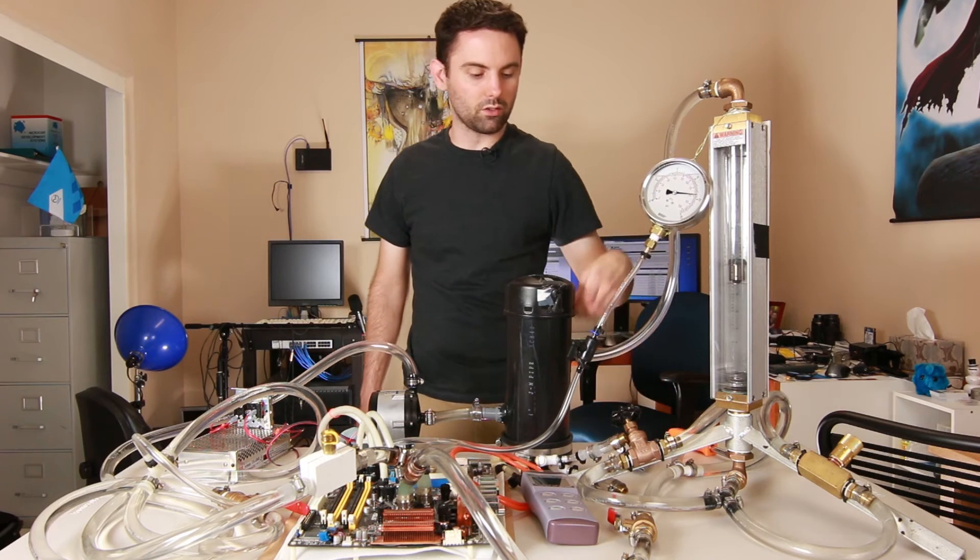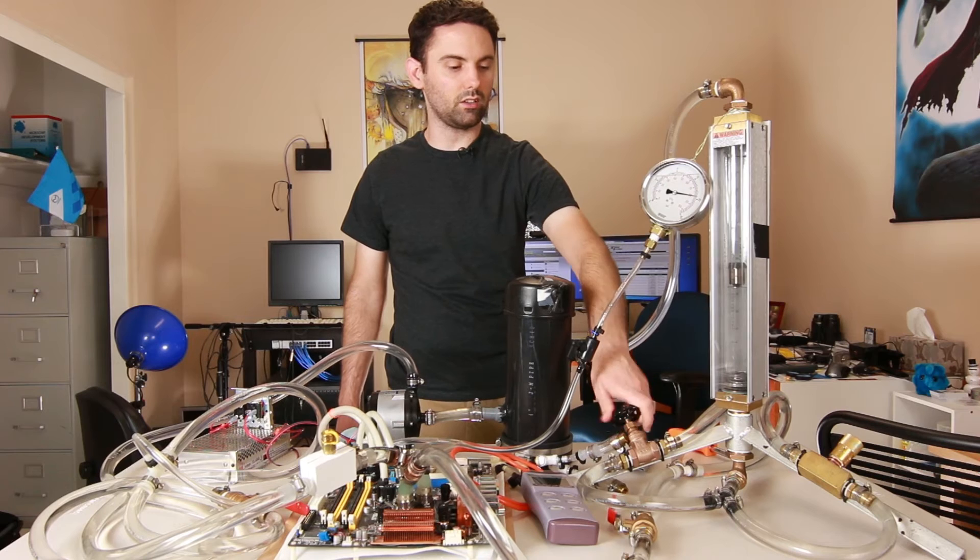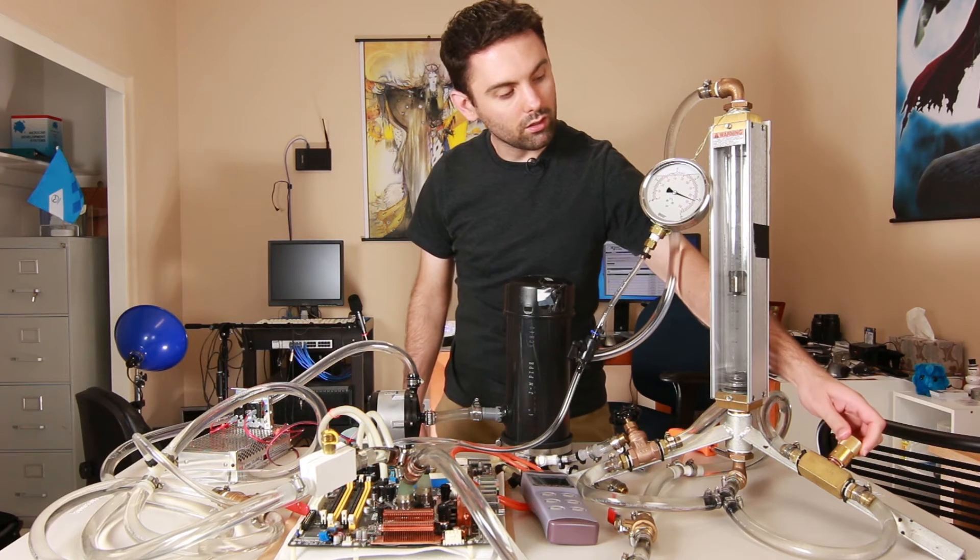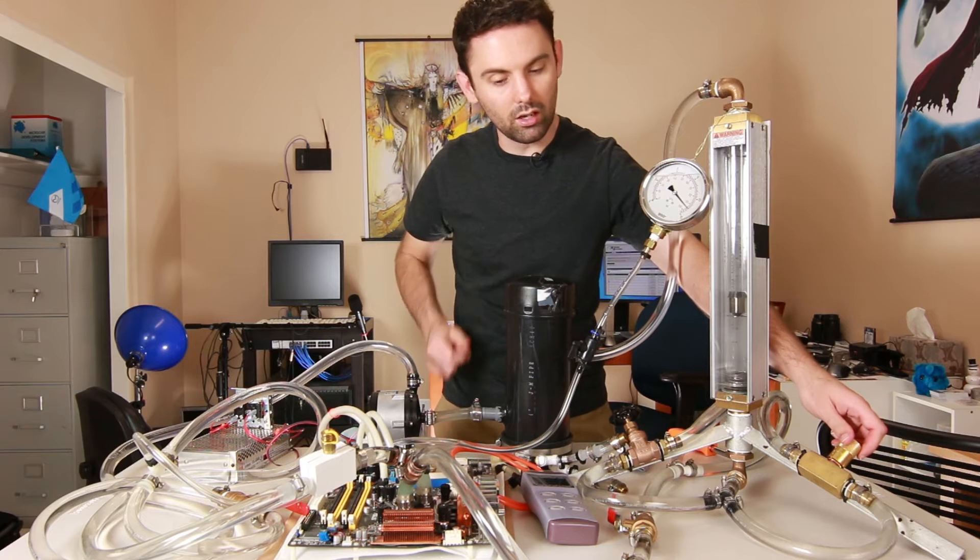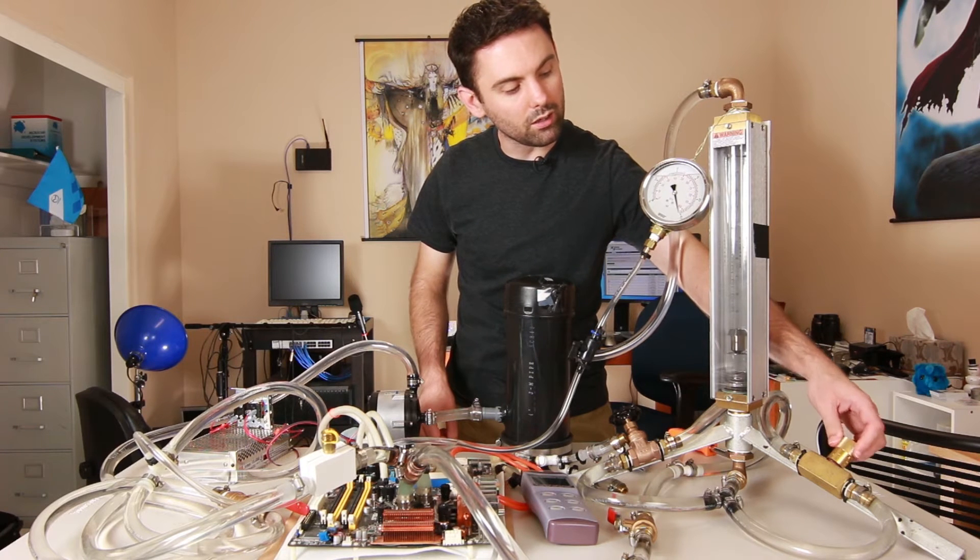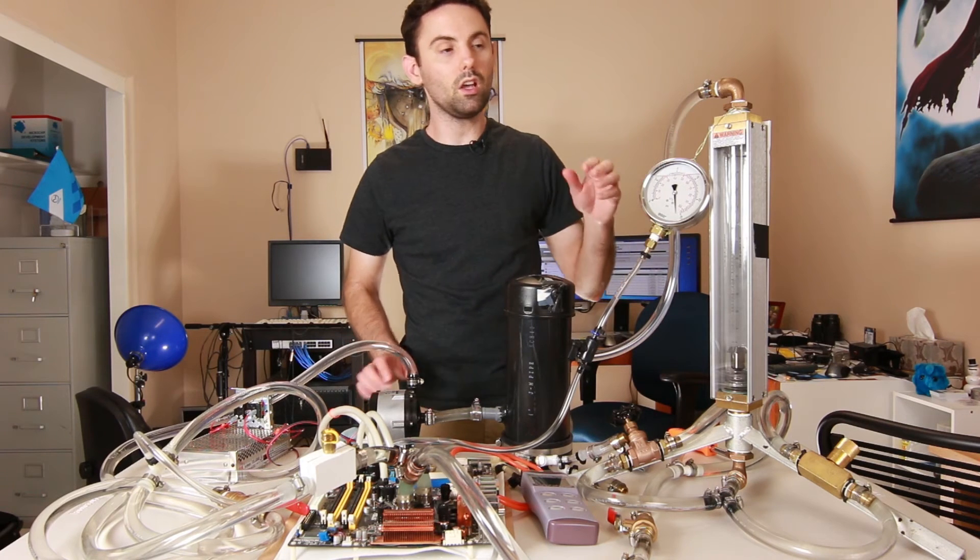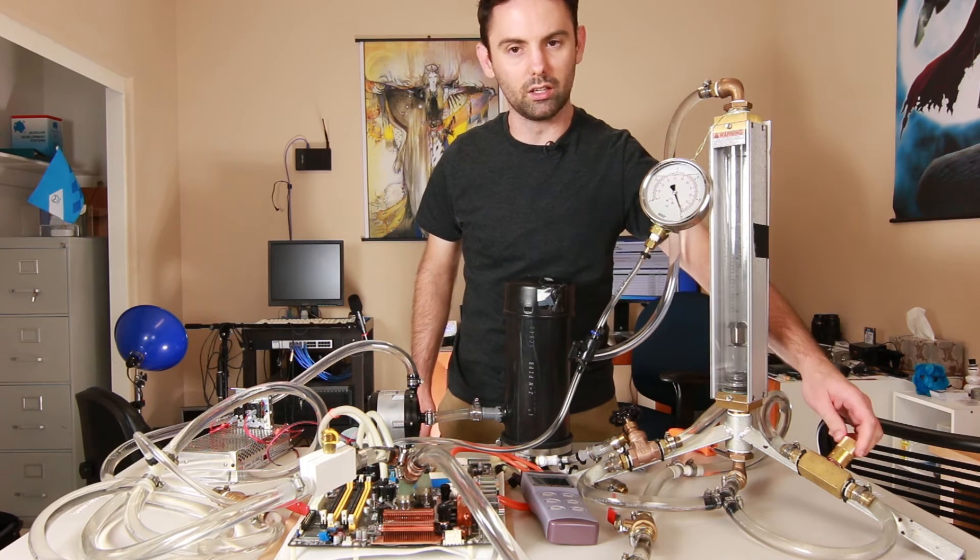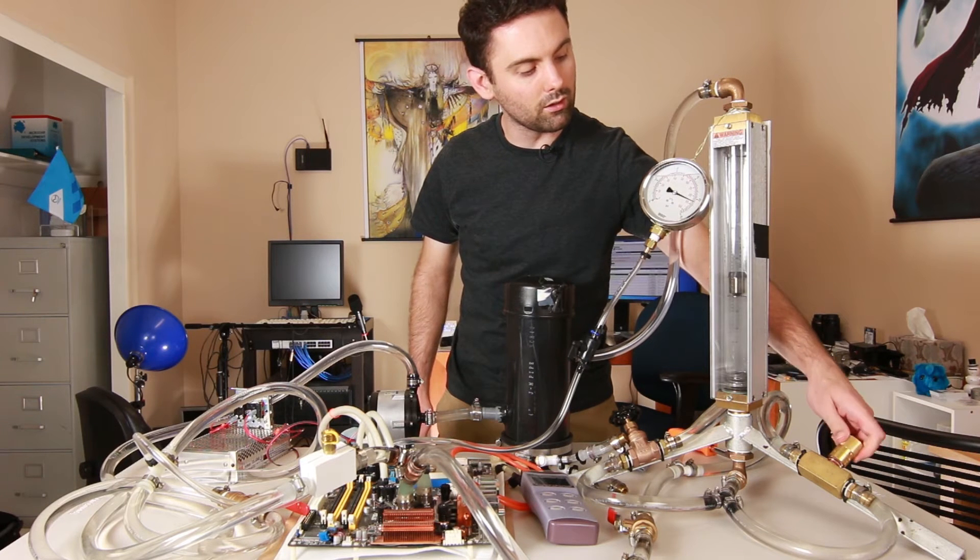Now if I start closing the valves, the control valves that I have on here, you'll note the float in the flow meter starts to descend, and it does so kind of slowly until I get to the needle valve over here. But as I close off the needle valve, it'll descend much more rapidly, and you'll see the pressure gauge increasing very quickly as I approach deadhead, which is basically when we reach zero flow, maximum head pressure. You'll see the gauge go off scale high, which it should be doing right, yep, there we go. So right there, this pump is capable of producing far more pressure than this gauge can actually read, but this allows you to see the relationship between flow and pressure. They're also kind of analogous to voltage and current in electrical circuit, flow obviously being analogous to current and voltage to pressure. And you see here I'm opening the valve up again, flow rate increases, operating pressure starts to drop as the valves open.